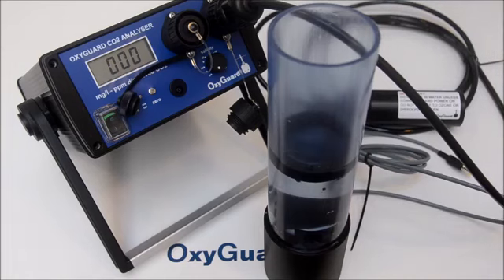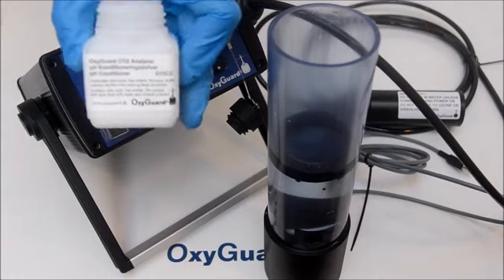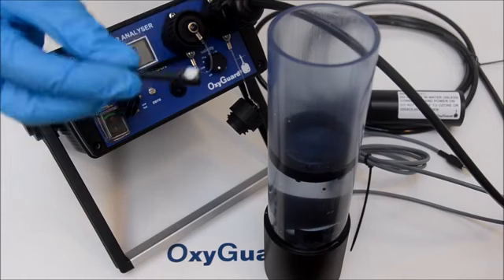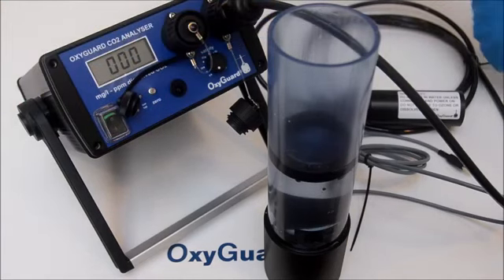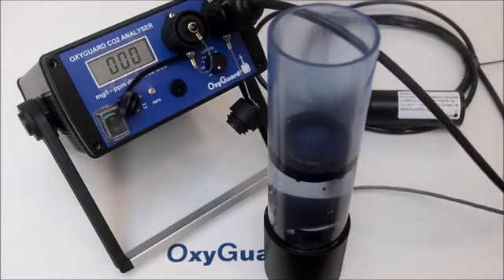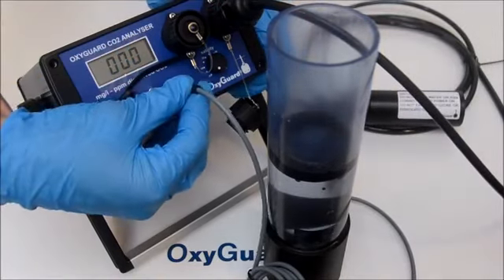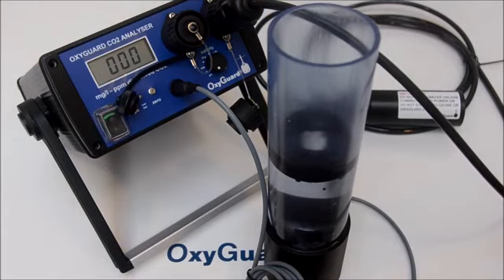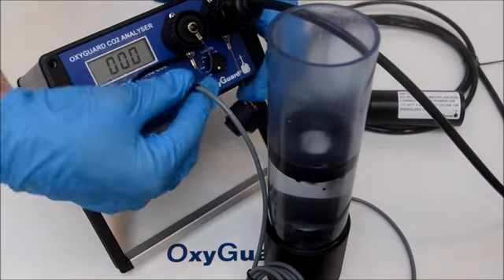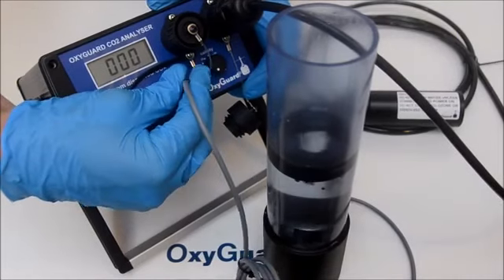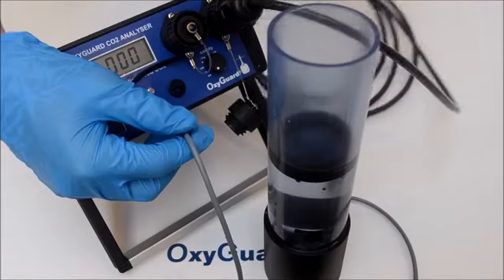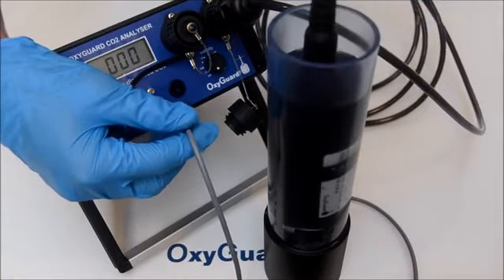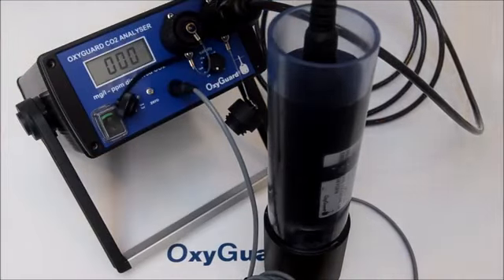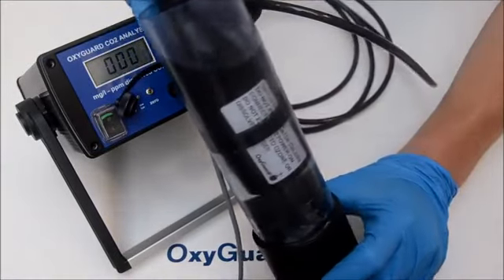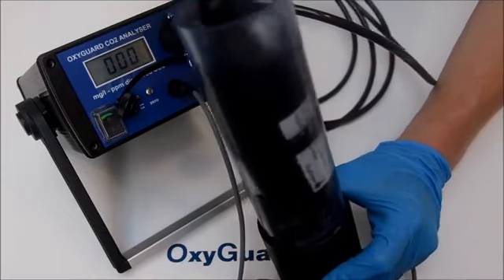Add 1 measuring spoon of pH conditioner. Stir until the powder has dissolved. Stop the stirrer, place the probe in the beaker, and start the stirrer again. Make sure that there are no bubbles under the probe. When the reading is stable, after about 5 minutes, write down the value. You will need this value later.